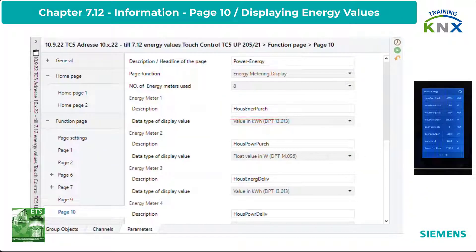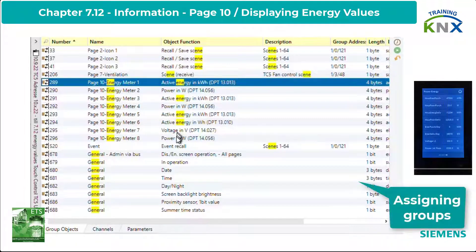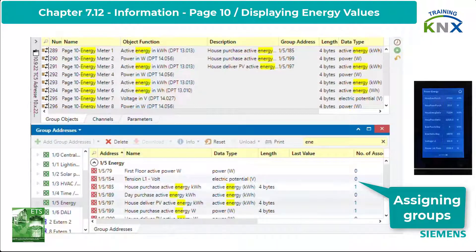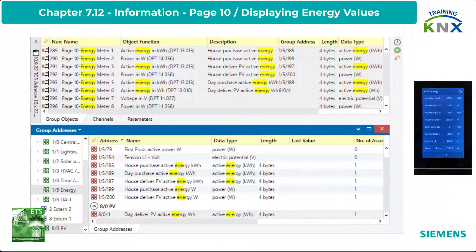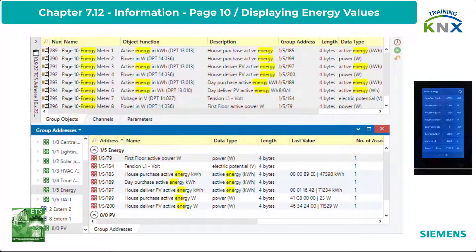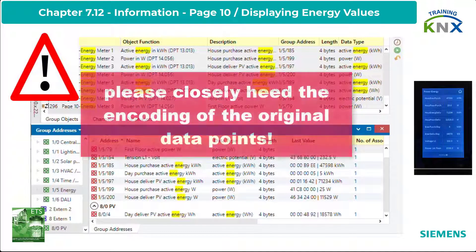Now I have created the 8 objects and linked them to the appropriate group addresses. Beside the used DPTs, there are others which refer to current in milliamps or amps and to voltage in millivolts. Please pay close attention to how the original data is coded, to see the correct values on the touch panel, and how often they are updated by the measuring and counting devices.